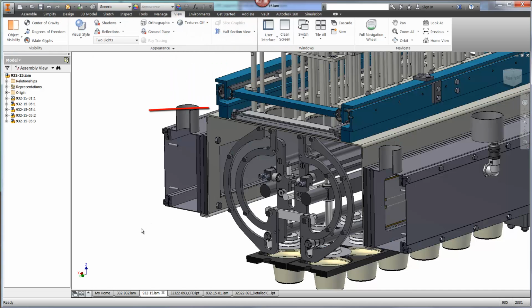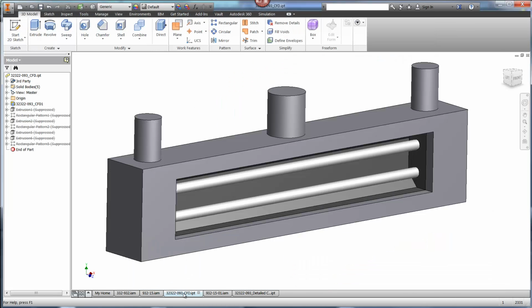Here you can see that the lids are grabbed one at a time and exposed to the UV light fixture to be disinfected. The lights are used 24 hours a day, and the bulbs are being replaced too often due to overheating. In an effort to work with the supplier, we can run an analysis to find out what can be done to improve on the efficiency of the design.